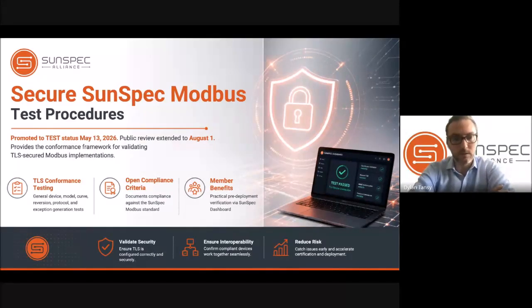So there's still time to download the spec, review it, and enter your comments or any issues that you have. And I really want to strongly encourage and invite people to actually begin implementing Secure SunSpec Modbus and stress testing using the test procedures in your own environments to help us uncover any issues or gaps that we might not have anticipated. There are already tools available to support Secure SunSpec Modbus, including one of the member benefits, SunSpec Dashboard, a piece of software included with SunSpec membership. It does already support Secure SunSpec Modbus, so you can encrypt it and test out your own devices. It includes device simulators and also a SunSpec Modbus client that has Secure SunSpec Modbus enabled.